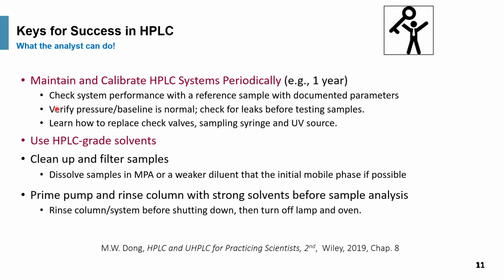It's nice to have a system to check system performance with a reference sample with documented parameters. We give you one example later on. The thing that you need to watch out for is you always try to verify things which can be easily confirmed, such as pressure. Pressure and your detector baseline are really important criteria before you actually do any sample injections. Check for leaks before testing samples.